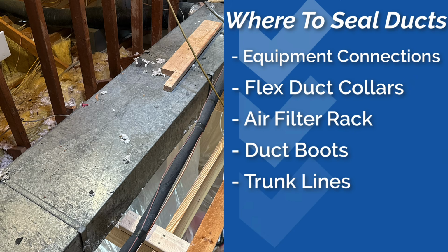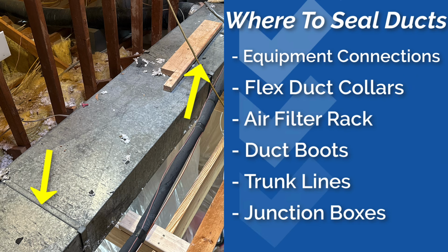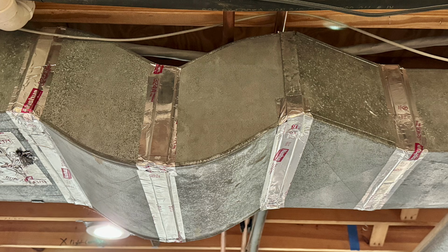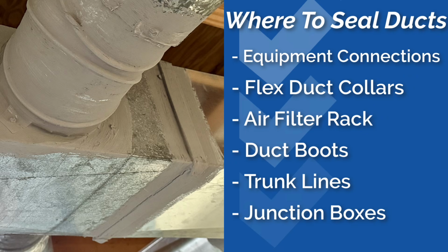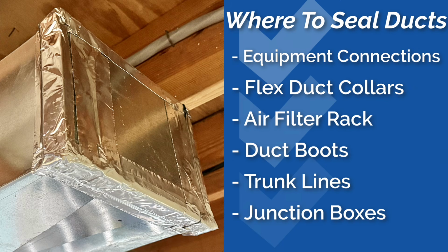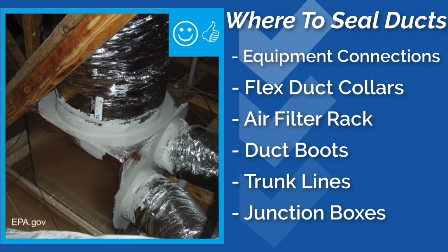The last one up here are trunk lines and junction boxes. With trunk lines, if you have a metal trunk line, wherever you see these metal straps, that's what connects 2 pieces of sheet metal ducts together, and those straps need to be sealed on both sides with either metal tape or duct mastic, or you could even use silicone caulk if you wanted to for this purpose. Make sure every one of those straps, including the ones on the ends of the trunk lines, are sealed really well. So with junction boxes, you want to make sure that any collars or supply branches that connect into those junction boxes are sealed metal to metal with duct mastic. Do not seal the insulation jacket to the insulation jacket, as this will still allow for duct leakage to happen inside of the insulation, and ultimately it doesn't really help anything.